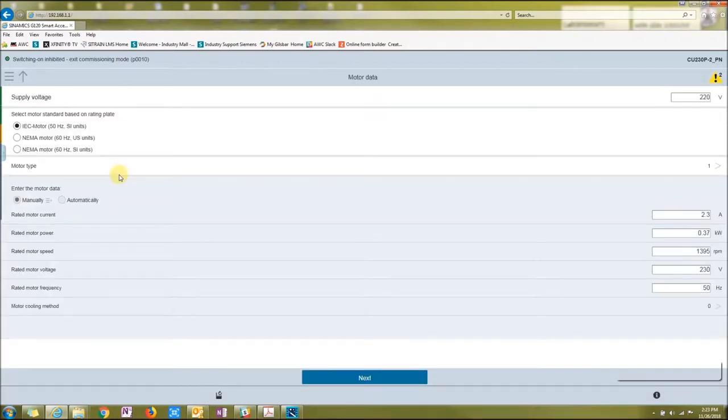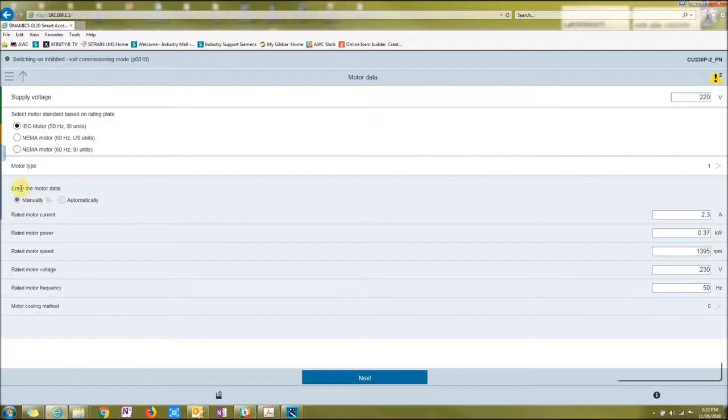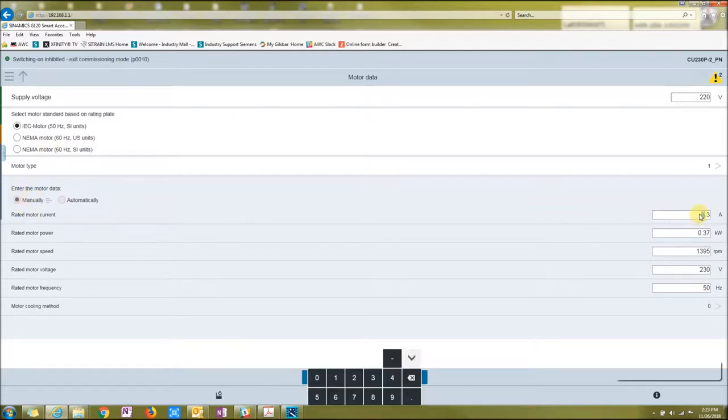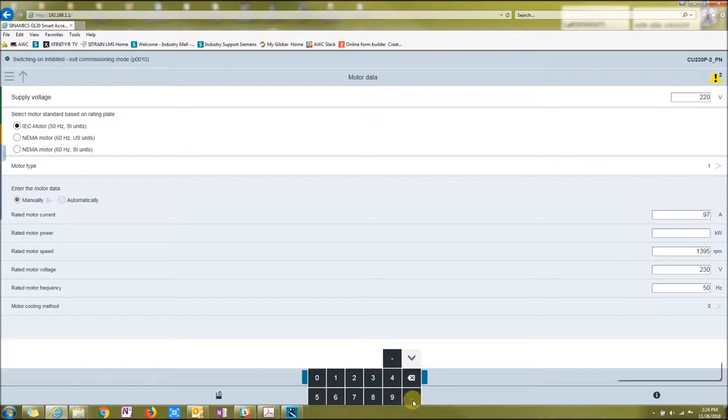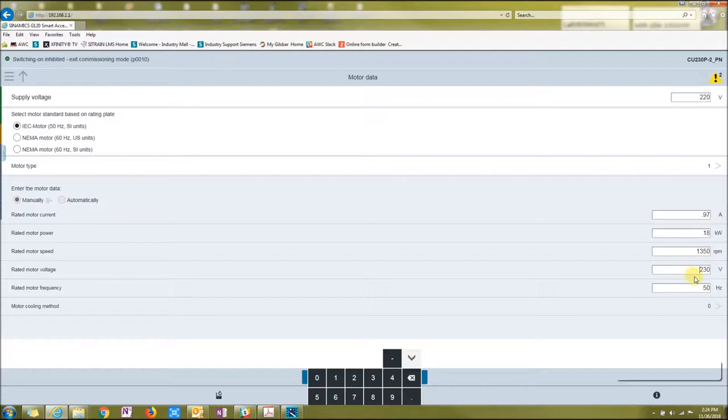My supply voltage is going to be 220 because I'm on a demo unit. I have an IEC 50 Hertz, and I am going to manually enter in the parameters. I'm going to click on my amps and it's going to be 0.97. My KW is going to be 0.18. My RPMs is going to be 1350. My voltage is going to be 230. Hertz is going to be 50.